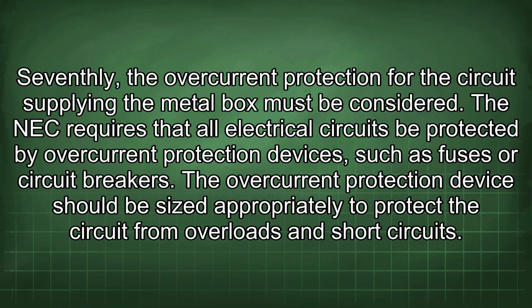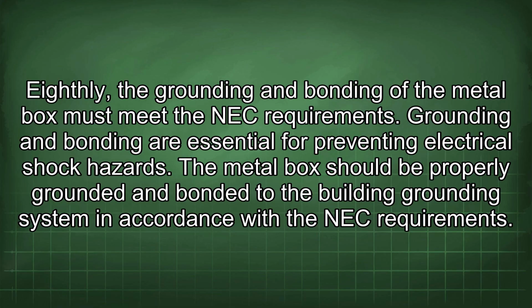The NEC requires that all electrical circuits be protected by overcurrent protection devices, such as fuses or circuit breakers. The overcurrent protection device should be sized appropriately to protect the circuit from overloads and short circuits. Eighthly, the grounding and bonding of the metal box must meet the NEC requirements. Grounding and bonding are essential for preventing electrical shock hazards. The metal box should be properly grounded and bonded to the building grounding system in accordance with the NEC requirements.